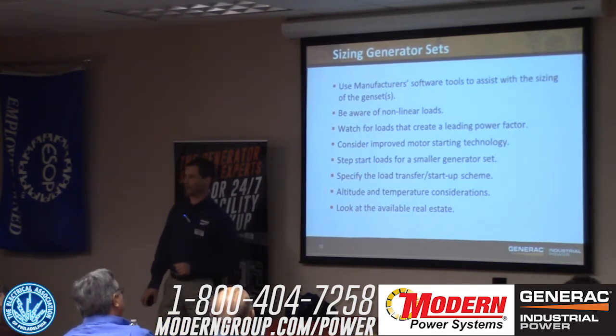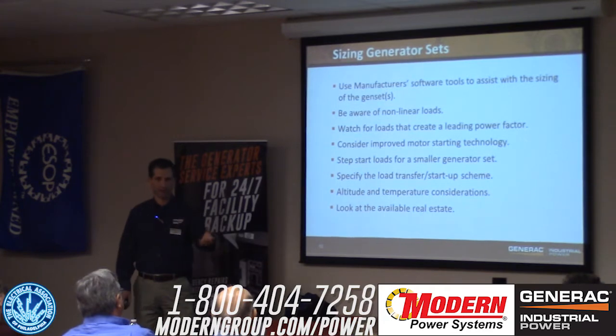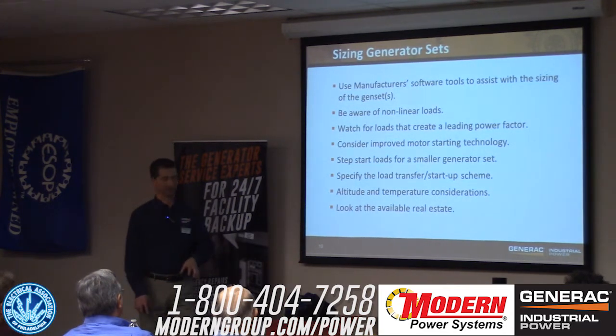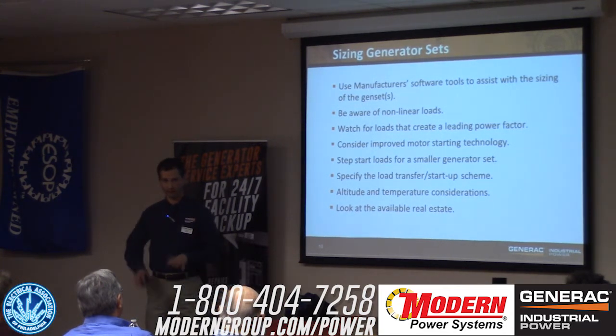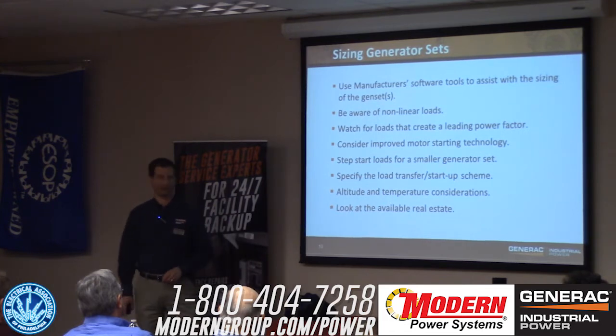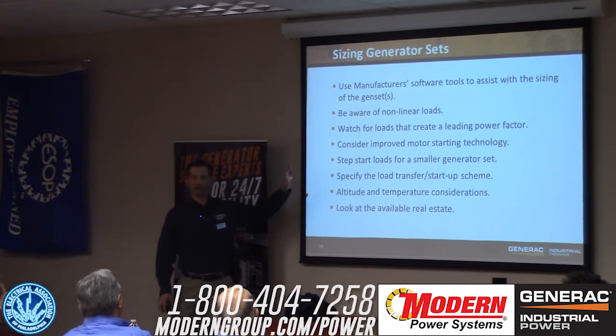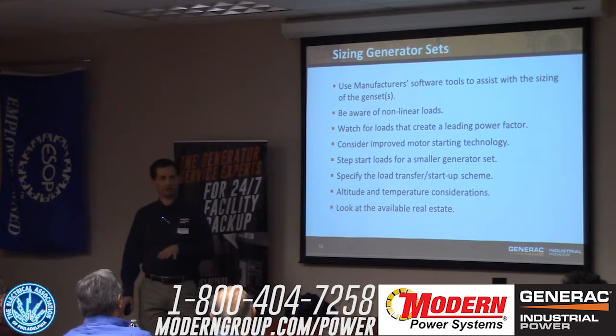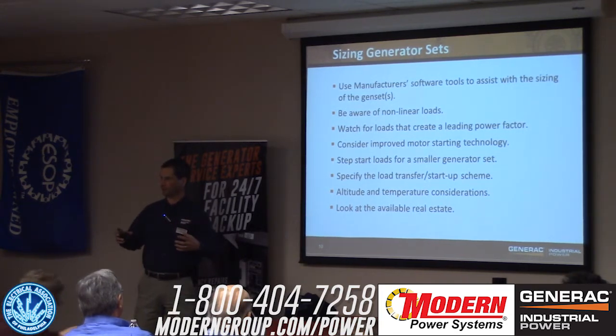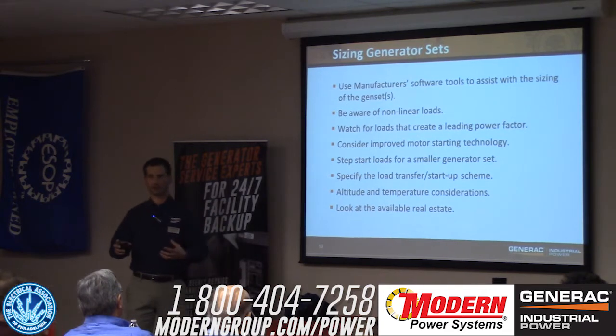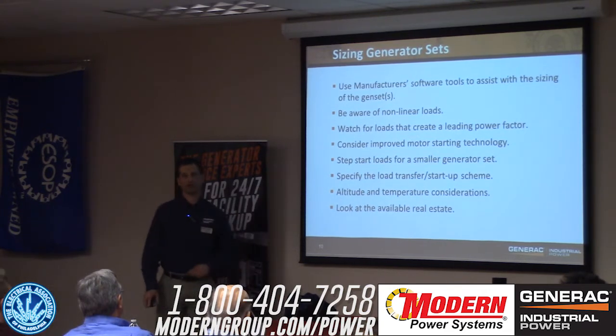Anything that creates a leading power factor, if you've got a little data center or UPSs stuck throughout your building, if those have caps in them, they can sneak up on you and cause a leading power factor. Generators don't like that. They get unstable and they become very unhappy quickly. A place where you can add value for your clients. If you've got some larger motors that you've got to start, motors want some serious current when you start them across the line. And that's going to drive your alternator size. You may have to upsize an alternator. Think about changing out that starter.